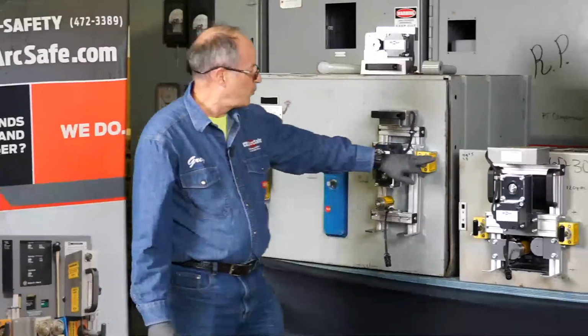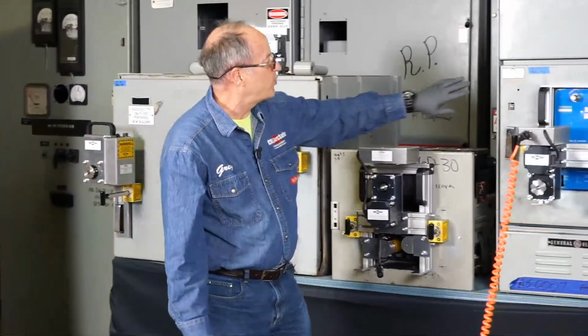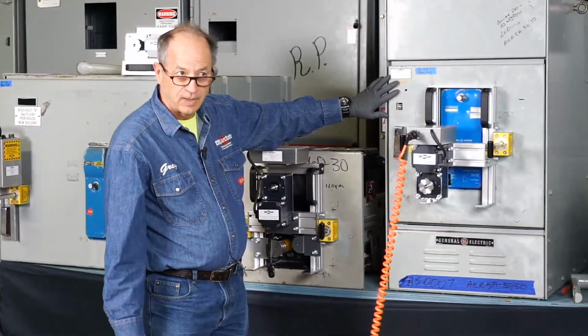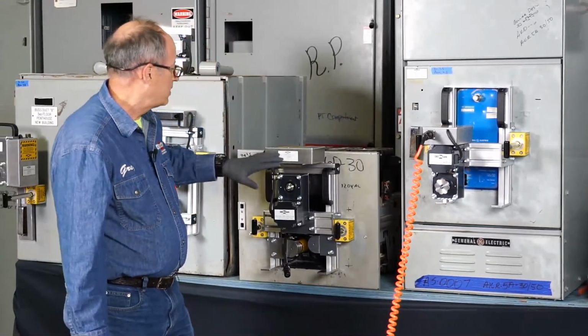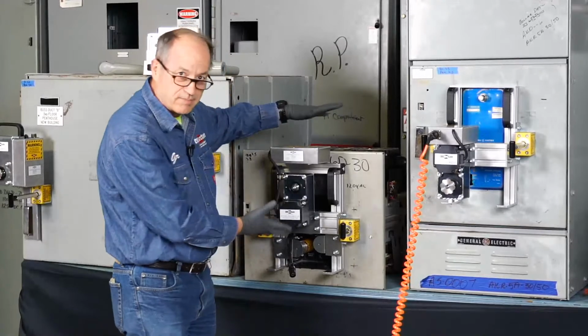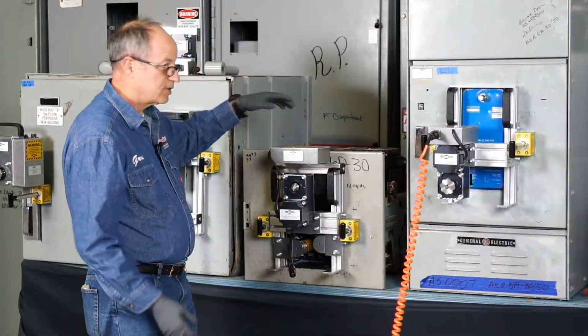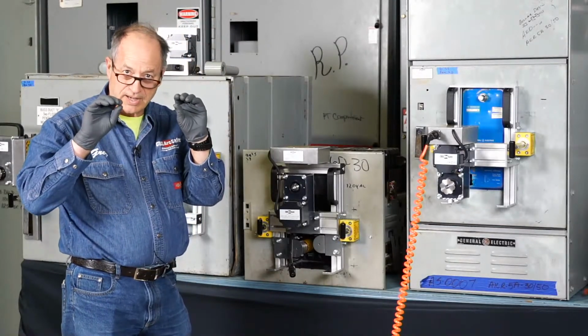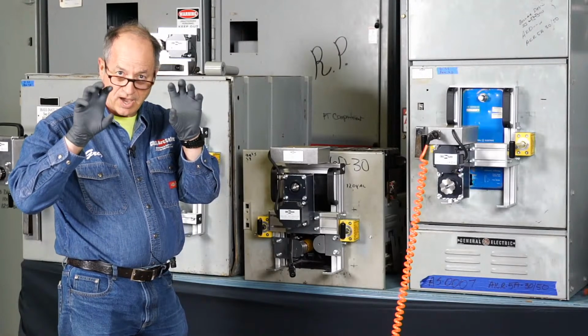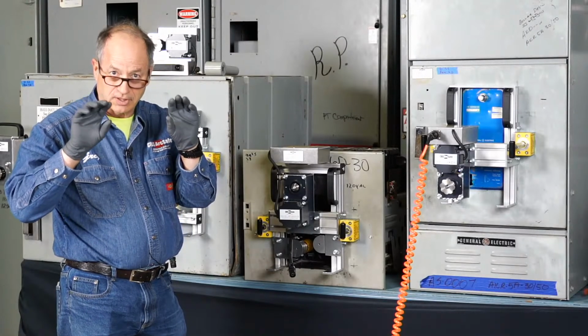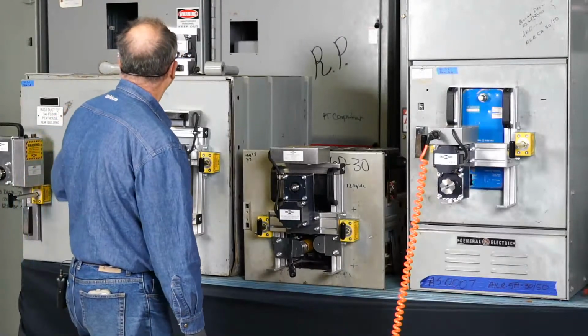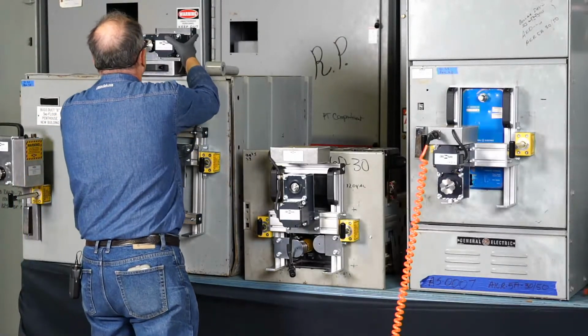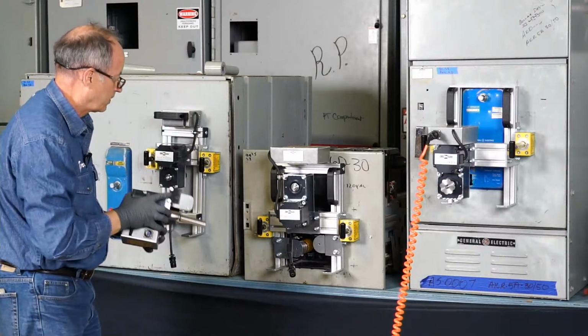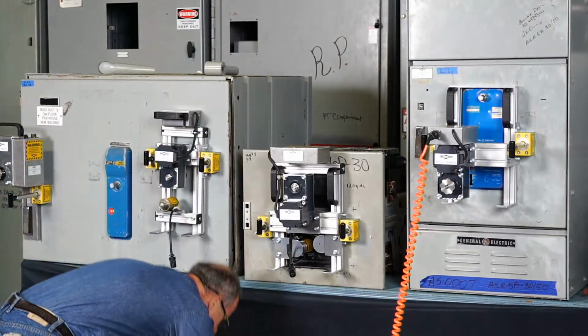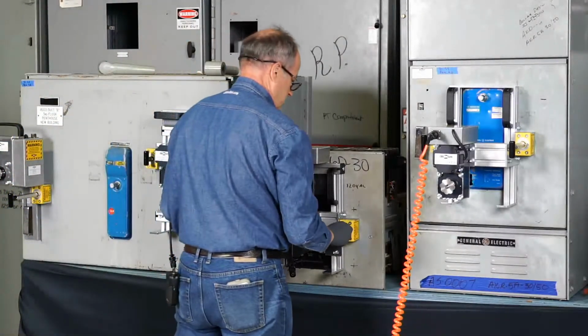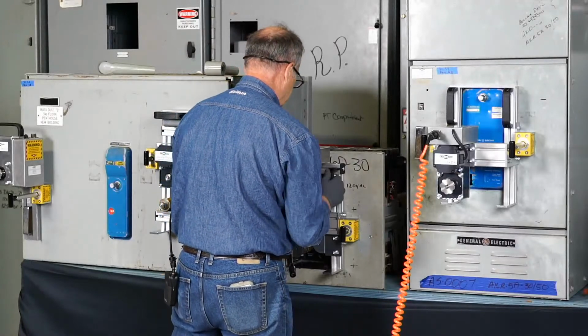This one would be 4.5 and 3.8. This one would be 5.0 and 4.0. And that's based upon the size of this breaker physically, the mass of it. And if we were able to turn it around, we'd look at the amp frame size to see how many fingers are back there on the finger clusters. So the way that this works, we'll go ahead and put this on here. Okay. After we take off the RSA, let me get that done first. My mistake. All right. I'm going to set this off on the side now.